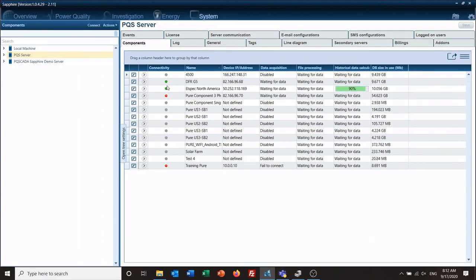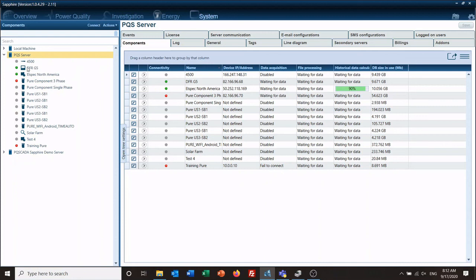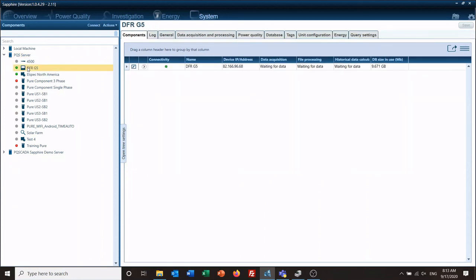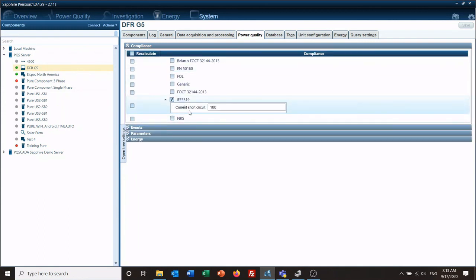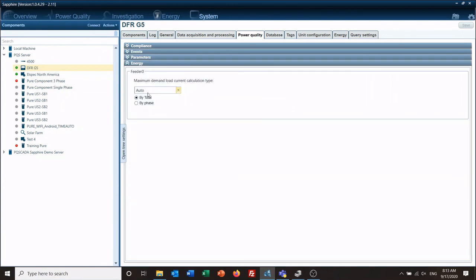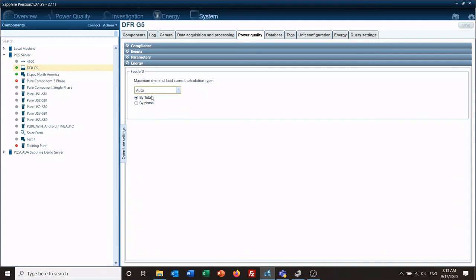Going back to system, we need to check that this device is set up to run the 519 report. Click on it, go to power quality, and under compliance make sure that the 519 is checked. You can input the short circuit current here or leave that blank. Under energy, you'll find the maximum demand load current calculation type. Auto allows the software to determine what the demand load current is; manual is if you know what it should be and want to input it directly. I'll leave it as auto to ensure I get a good report.